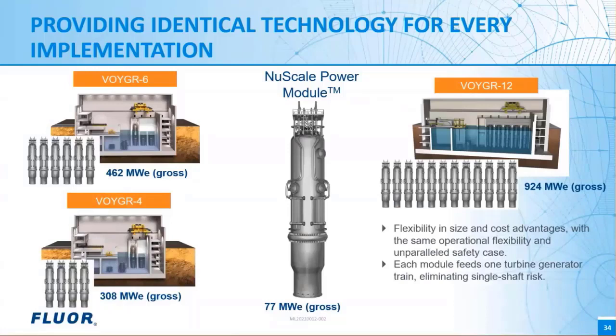I mentioned the flexibility and scalability of the NuScale plant. Here are several versions, as I discussed, that we're looking at with various clients. The standard plant is the VOYGR-6 in the upper left, but we're also talking with clients on the 4-module and 12-module versions. Note the multi-bay reactor building can be constructed and started with any number of modules installed. Thus, you can start generating revenue immediately upon installing and starting the first module, while later modules can be installed later and started as needed. As I mentioned, workers can be in the reactor building while all 12 are at power, so refueling and installation of modules and removal of modules can occur at power.